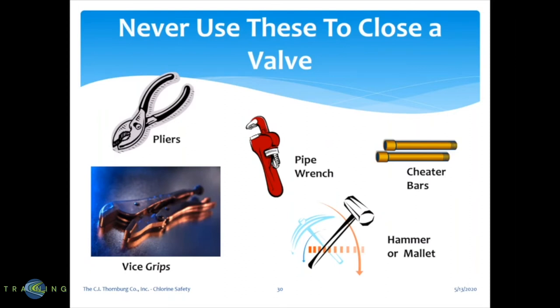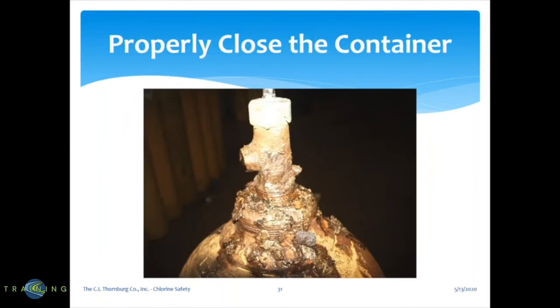Never use these tools to close or open a valve: don't use pliers, vice grips, pipe wrenches, hammers, cheater bars, or anything like that. We have chlorine wrenches specifically designed for opening and closing the valves on cylinders. When you are done with a chlorine or sulfur cylinder, make sure that you close the valve properly and close it tight so it does not leak.